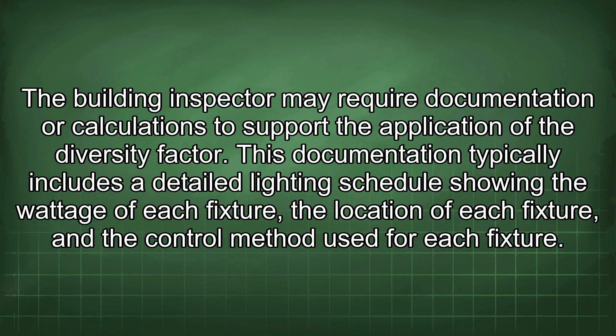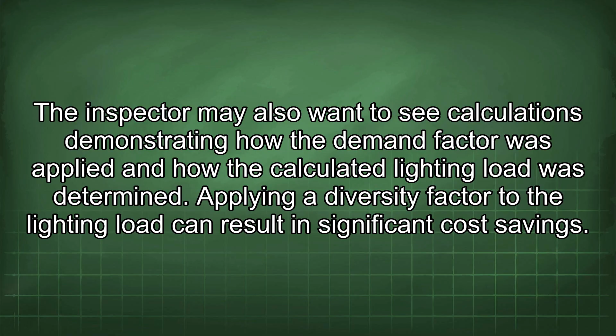This documentation typically includes a detailed lighting schedule showing the wattage of each fixture, the location of each fixture, and the control method used for each fixture. The inspector may also want to see calculations demonstrating how the demand factor was applied and how the calculated lighting load was determined. Applying a diversity factor to the lighting load can result in significant cost savings.